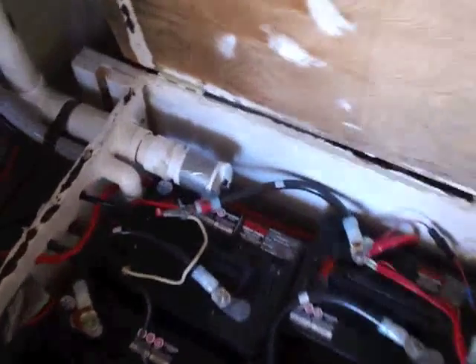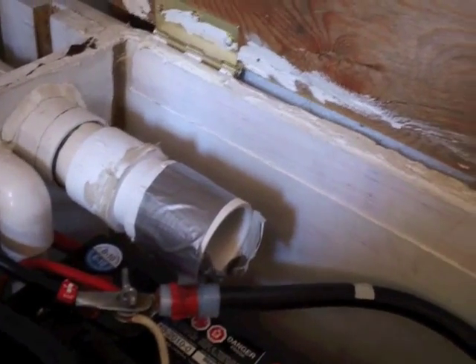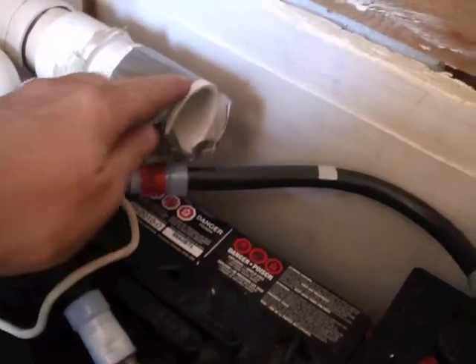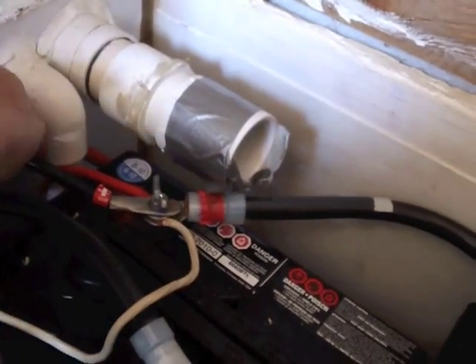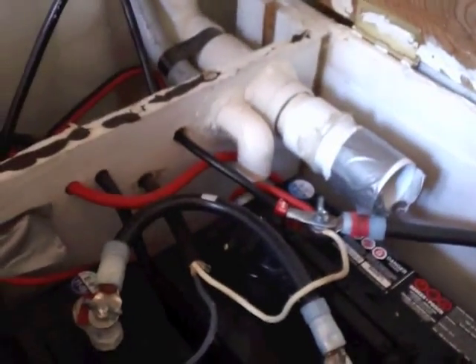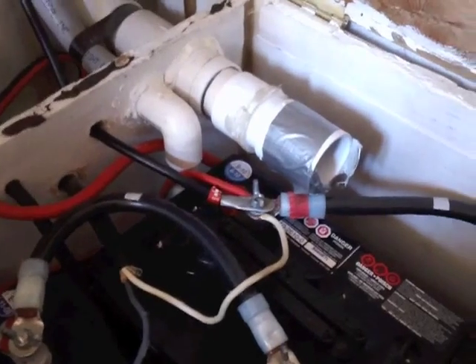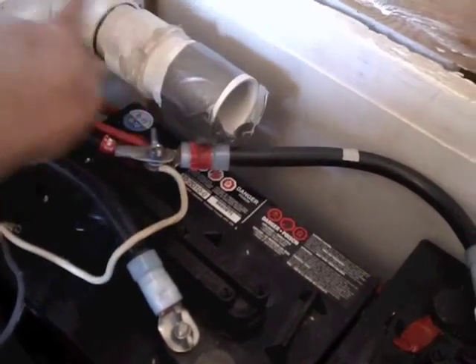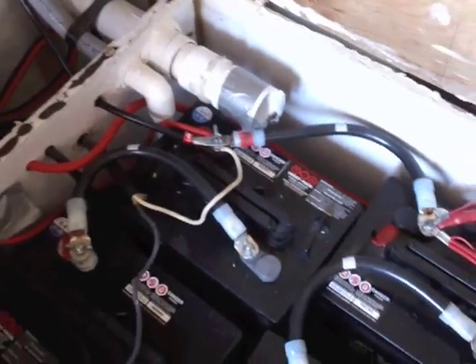I've got my passive venting system here. Once the hydrogen in these batteries builds up, the lid will be closed, it'll go through here and out, and the cool air will come in at the bottom. I've got caulking all around the outside of this box — it'll create a vacuum seal — so you get this passive effect: sucking cold air in, blowing warm air out. No electronics involved. It just does its own thing when it needs to.